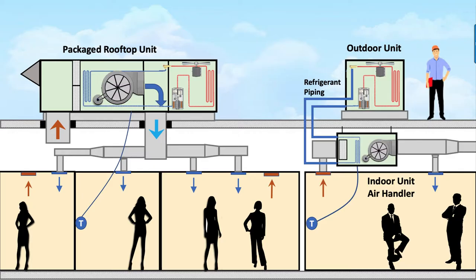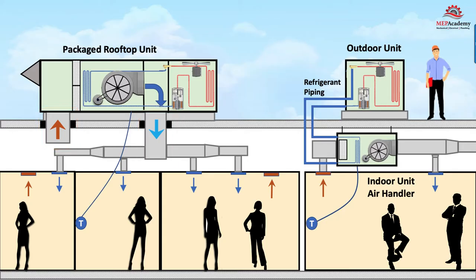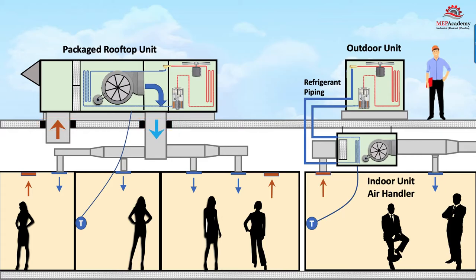HVAC split systems are convenient to use with existing buildings because it's much easier to route small refrigerant piping to the indoor coil than to run much larger air ducts using a rooftop package unit. As you can see, the rooftop unit needs large openings for the supply and return ducts to enter the building. The split system uses smaller copper tubing and requires a small opening in the roof or wall.